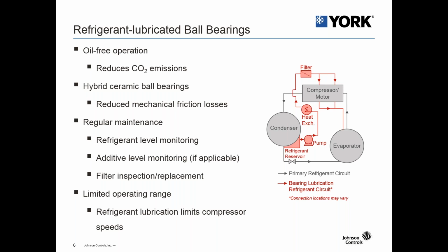So there's still refrigerant level monitoring that needs to be controlled to ensure that the refrigerant reservoir is charged enough. If there are additives required for the refrigerants, that would need to be monitored and checked as well. And there's still the routine inspection for the filter and replacements over certain intervals of operation. There's also limited operating range. So because refrigerant is used as the lubricant, there are still some limits that would be applied to maximum compressor speeds.